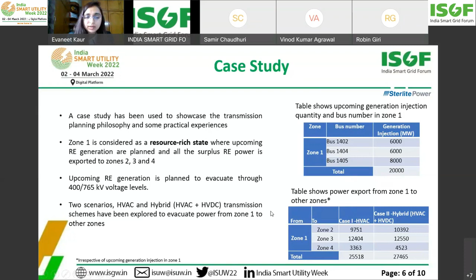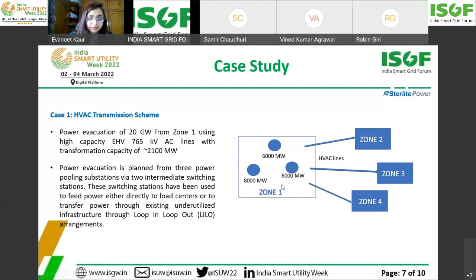In this scheme, power evacuation of 20 gigawatt from Zone 1 is planned using high capacity, extra high voltage 765 kV AC lines with surge impedance loading (SIL) of approximately 2100 megawatt. This power evacuation is planned using 3 power pooling substations via 2 intermediate switching stations. These switching stations have been used to feed power directly to load centers or to transfer power through existing underutilized infrastructure through LILO arrangements. In this scheme, power is evacuated through 765 and 400 kV pooling stations to 2 765 switching stations. The generating stations are interconnected to accommodate any line outages.